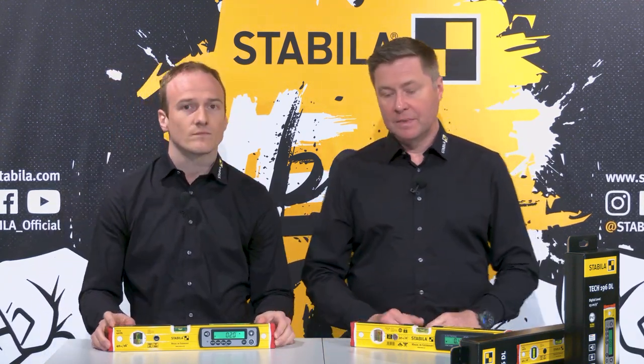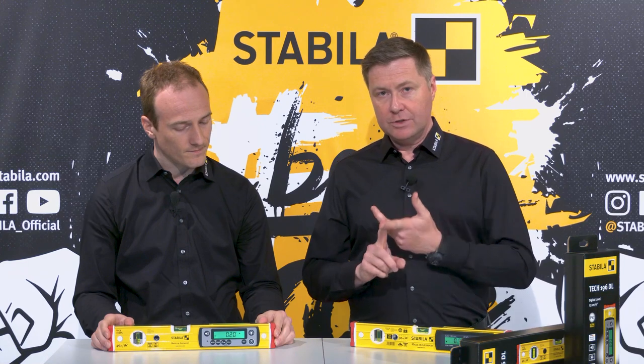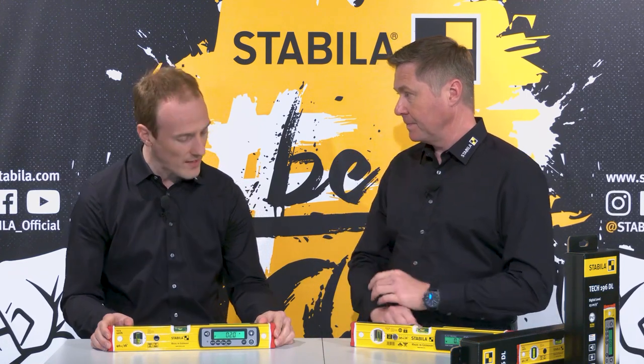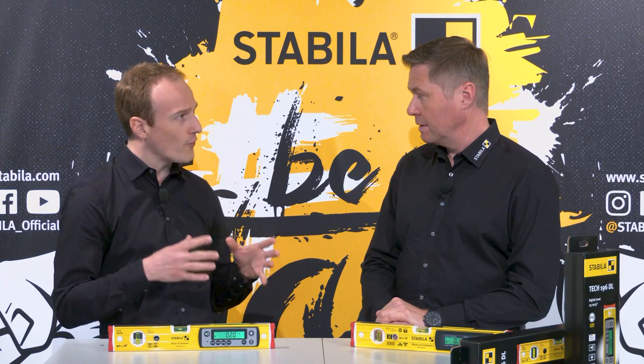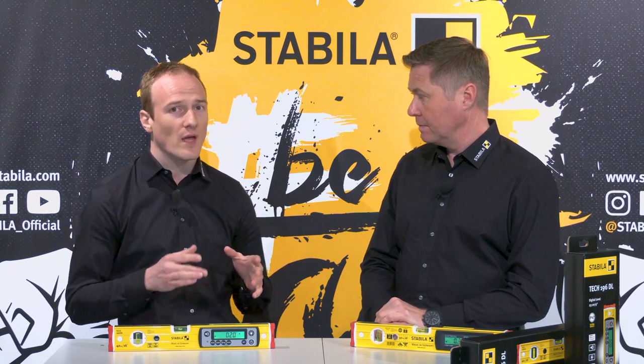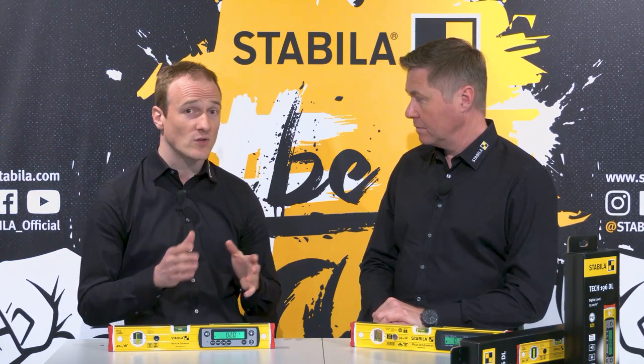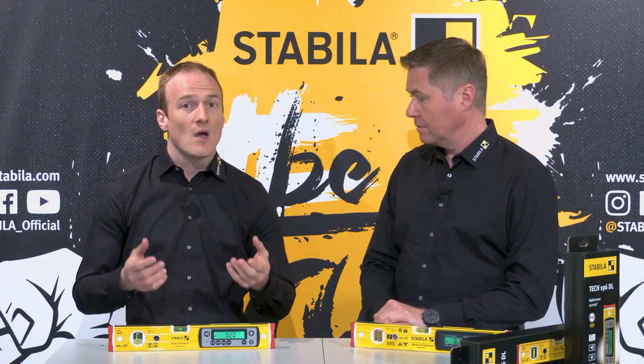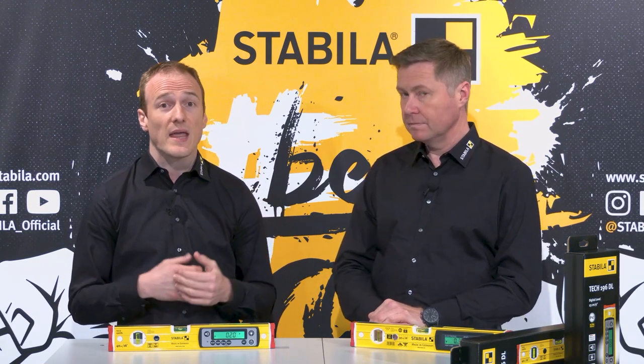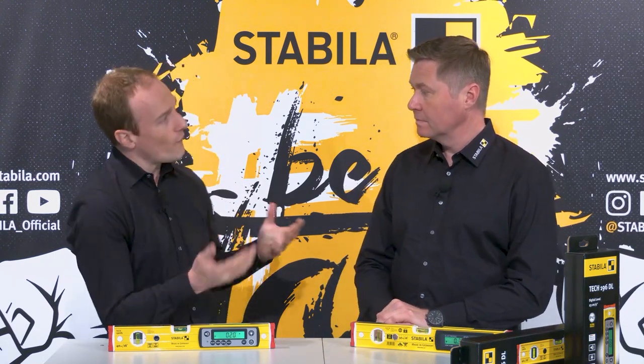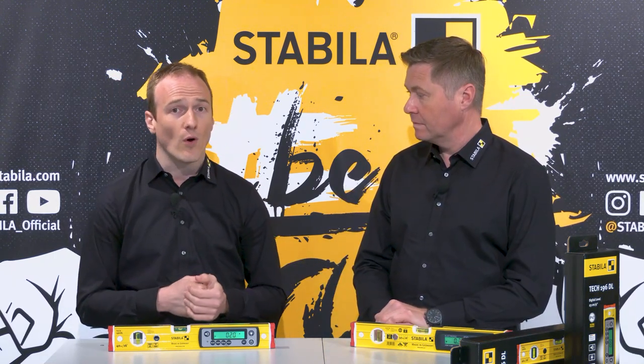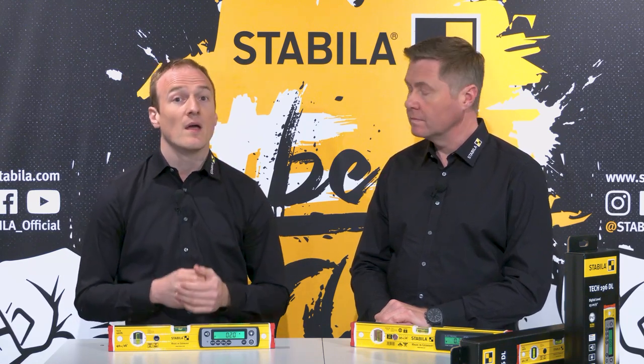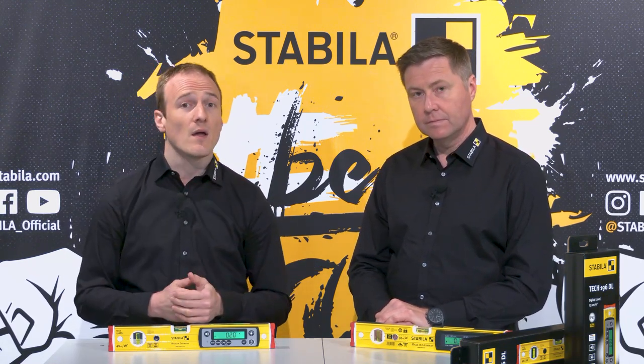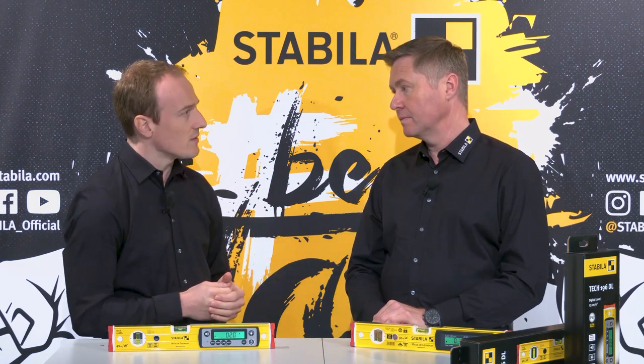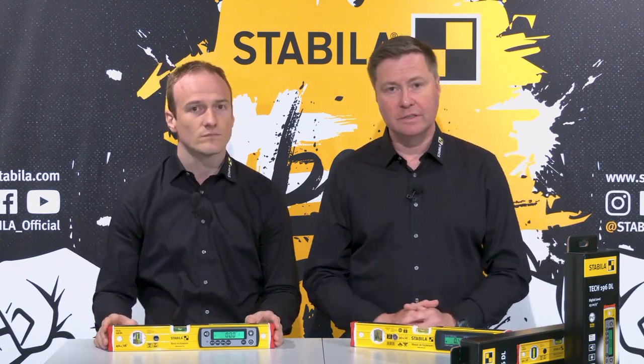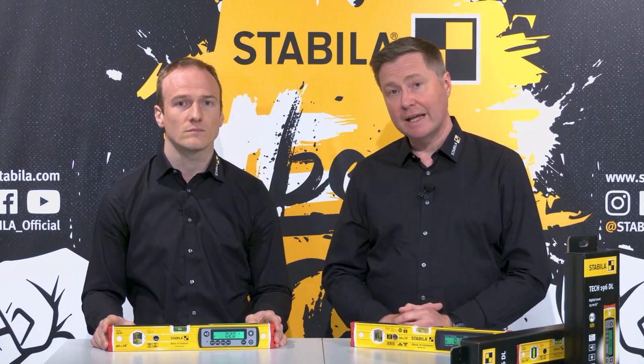That's quite a lot. Point three you mentioned concerned the robustness. That's right. Thanks to the new Calibration-free technology, no calibration of the electronics is necessary even after drops or temperature fluctuations. With the previous models, they had to be recalibrated at one or four positions in the event of major falls or fluctuations in temperature. This was then shown on the display, and you could do it yourself quite easily.